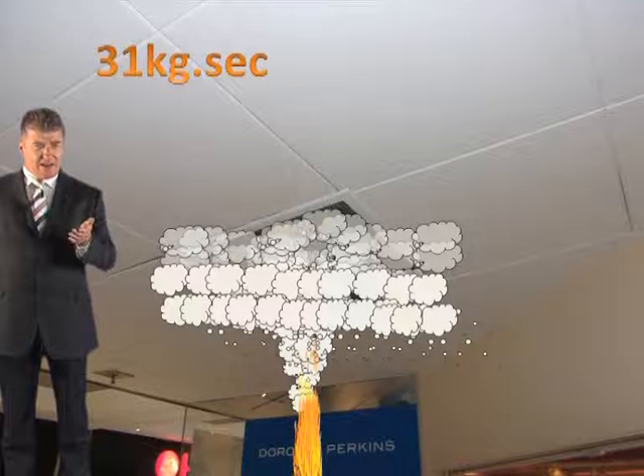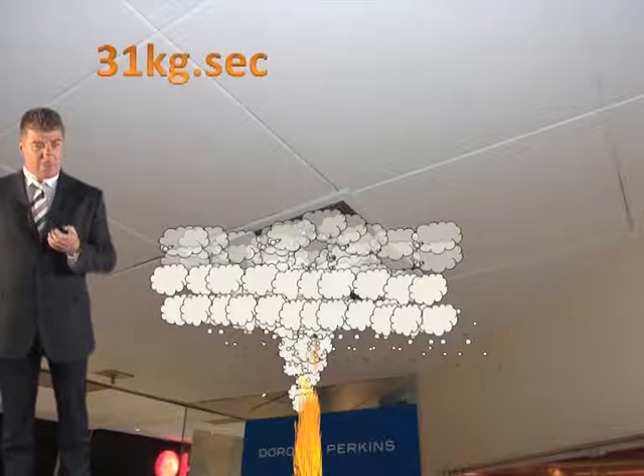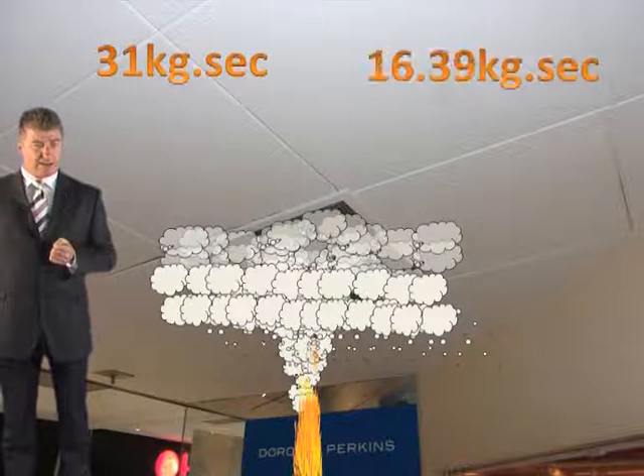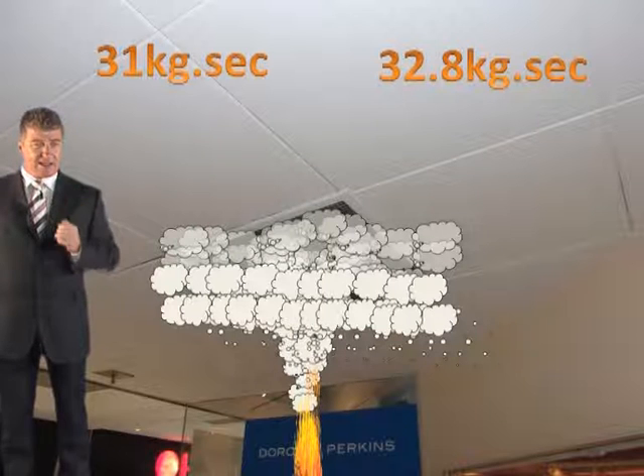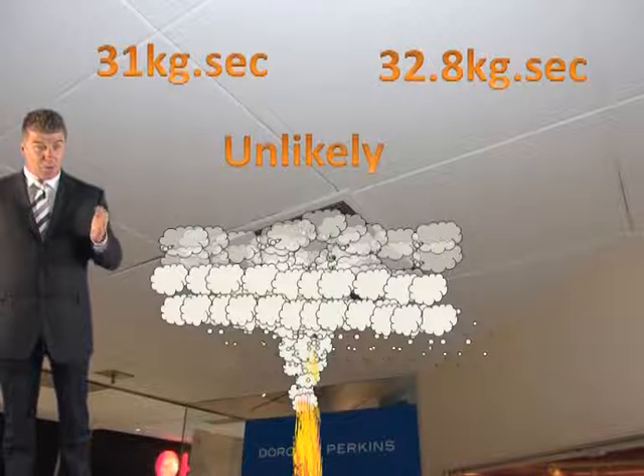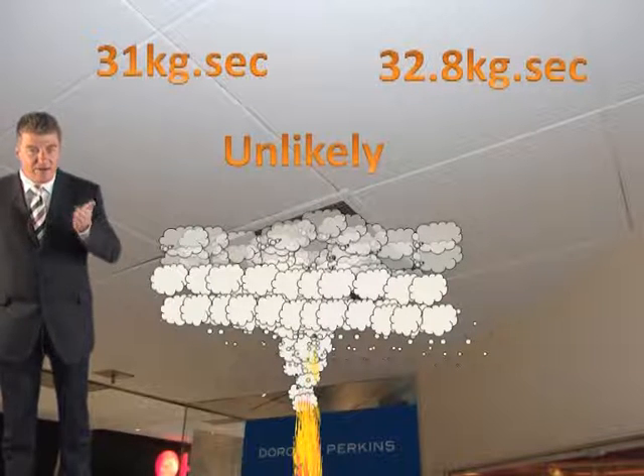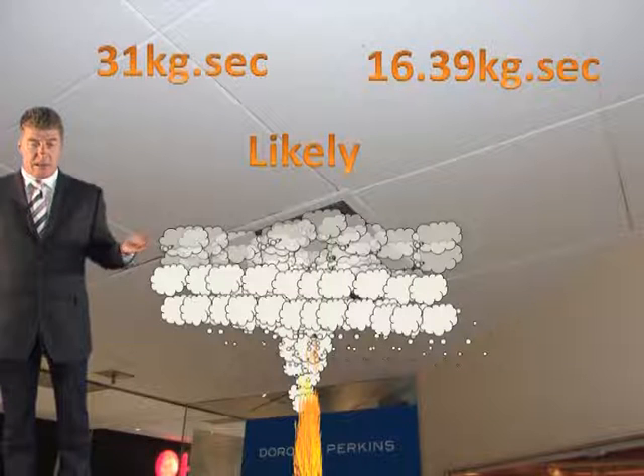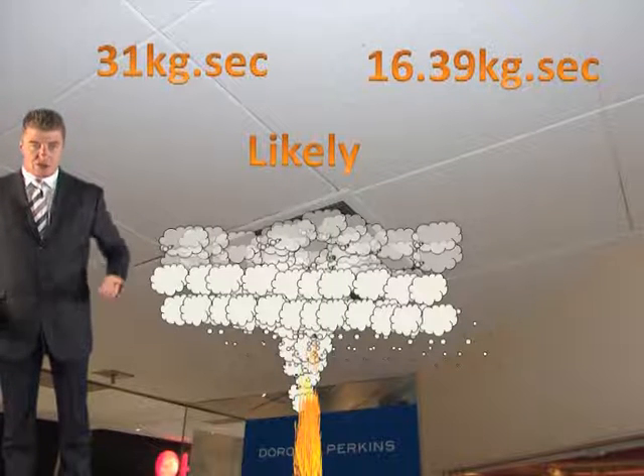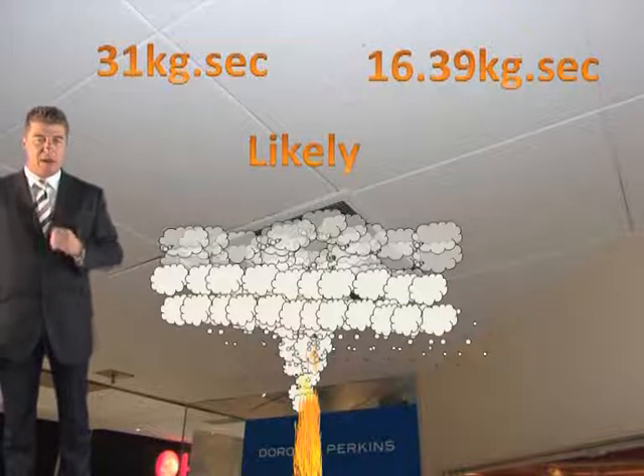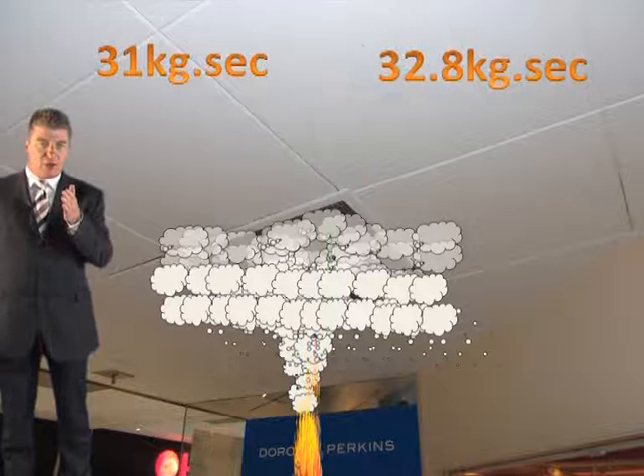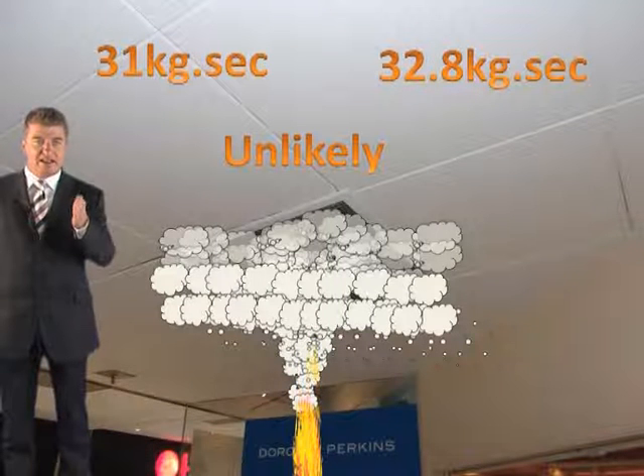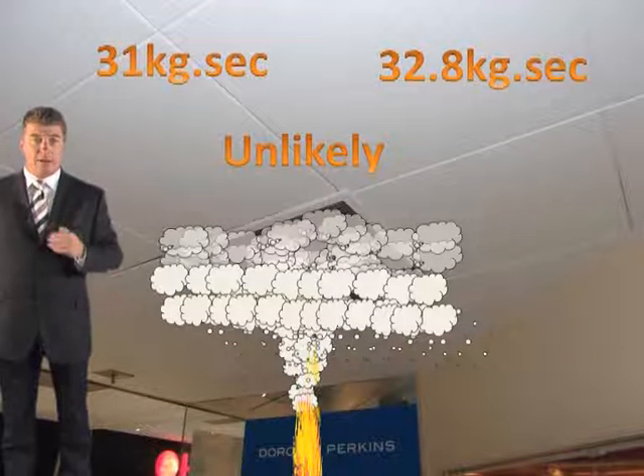plug hole and entrain air and not be efficient. That's it. So in this case, the smoke leaving each ventilator, we've said in the example, was 31 kilograms a second, and the mcrit is 16.39 kilograms a second, which means in this case, it is very likely that plug holing will occur. So you will get air entrained in, and you need to do something about it. One possible method is having more smaller vents in each reservoir, but it will plug hole.